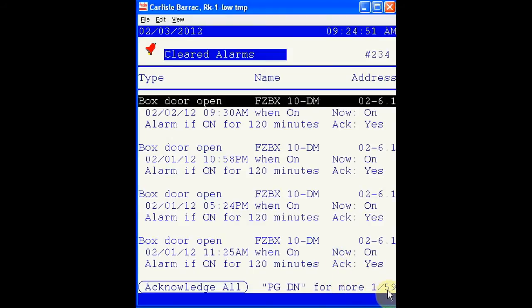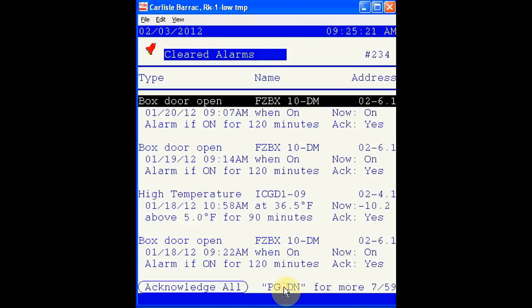We have available 59 pages worth of cleared alarms. At the top we can see that there are a total of 234 entries in this log. It's possible to acknowledge all alarms, but a confirmation must be made to ensure that is correct. It's possible to page down through several pages worth of alarms to find any alarms you might be looking for.